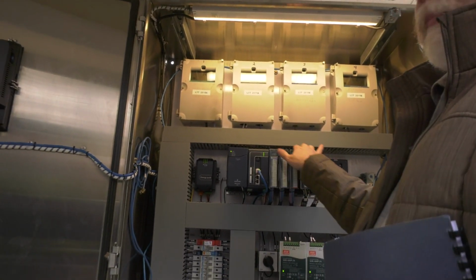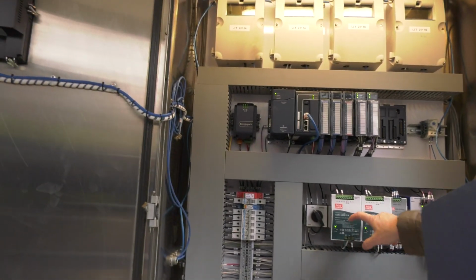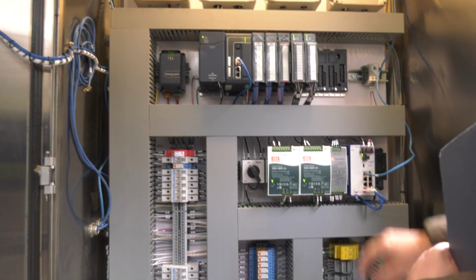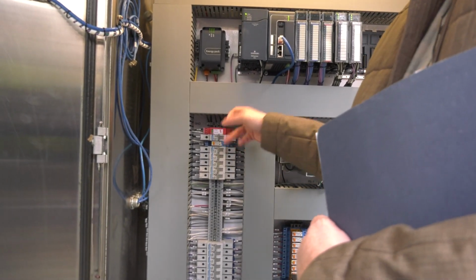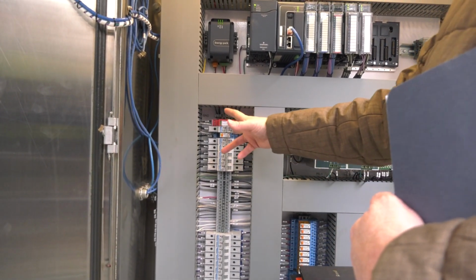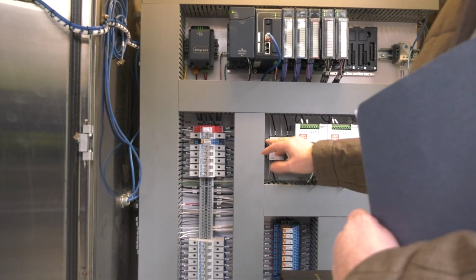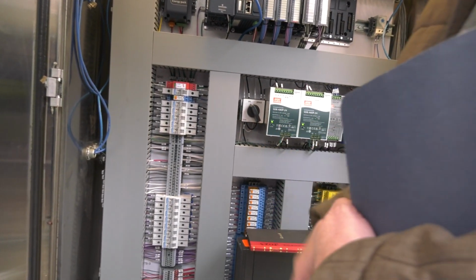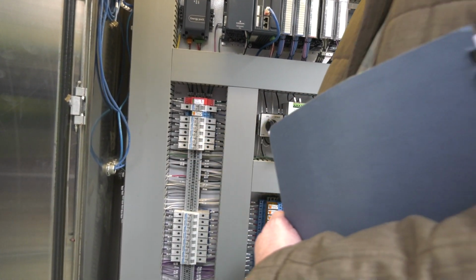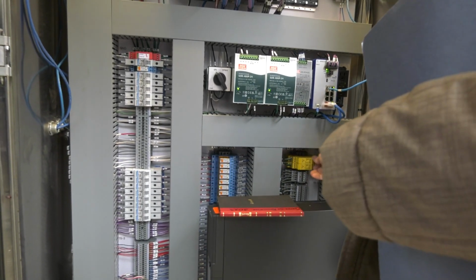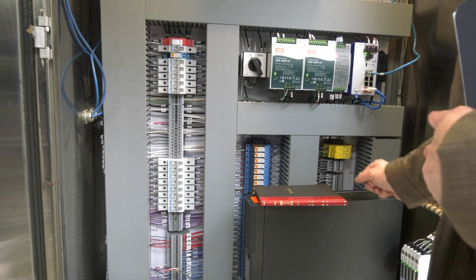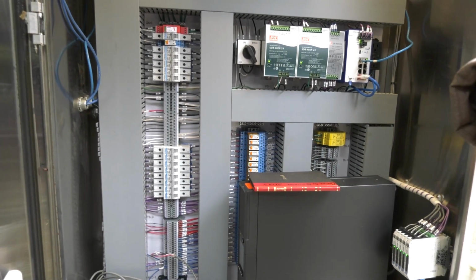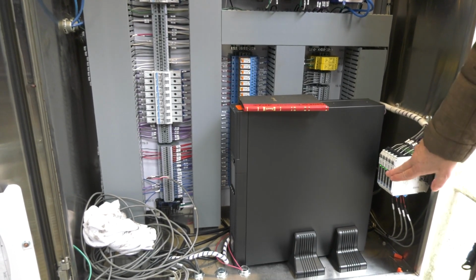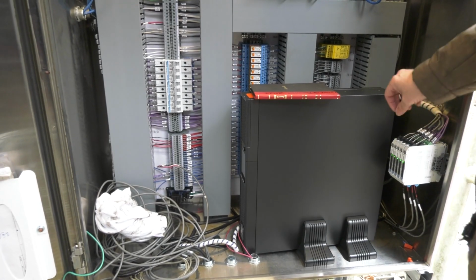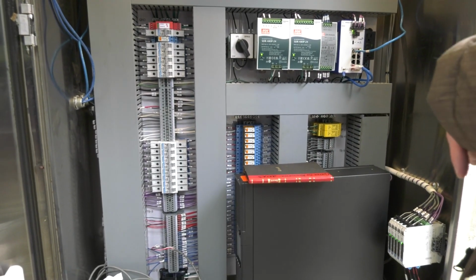All right. Your PLC, energy pack, redundant power supplies with a redundant module, Ethernet switch. Again, your 120 surge suppressor. This is your main breaker, so if you have to kill the power, flip this. And again, if you want to bypass the UPS, just put it in bypass. That'll kill 120 volts. Breakers, self-explanatory. The 4 to 20 surge suppressors. Again, these modules pop out, and it's make-before-break, so if the module goes bad, just pull it out and you won't lose any signals. You've got your intrinsic safety barriers here. If they need to be replaced, again, the terminals pop off. It's a pretty easy replacement. No dip switches, no configuration. That's it for this.